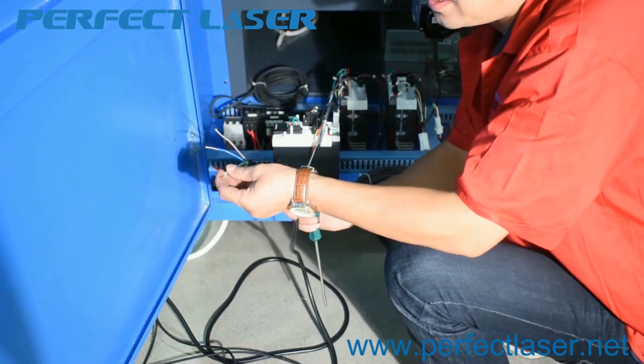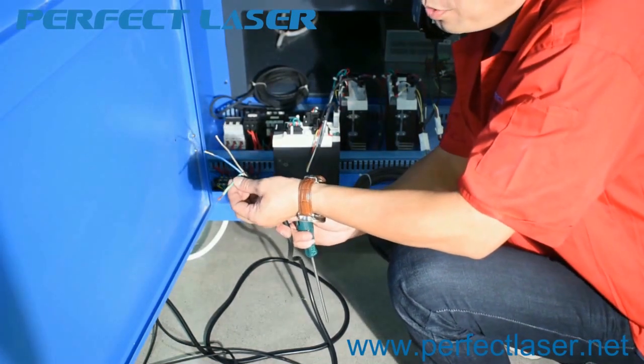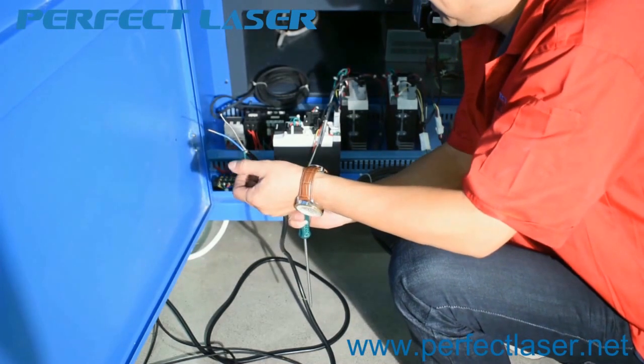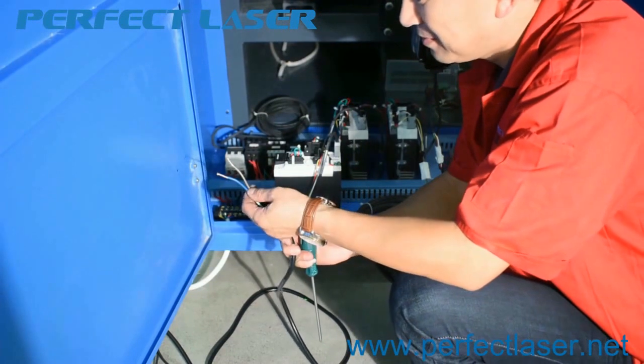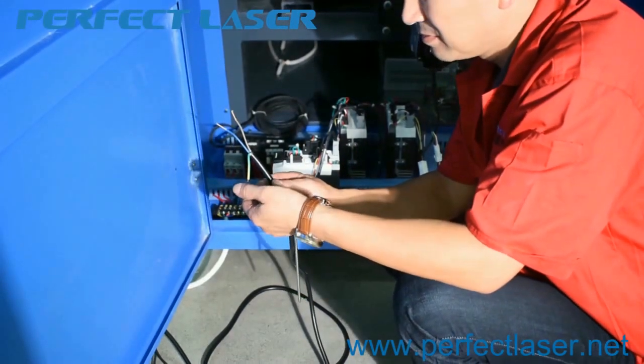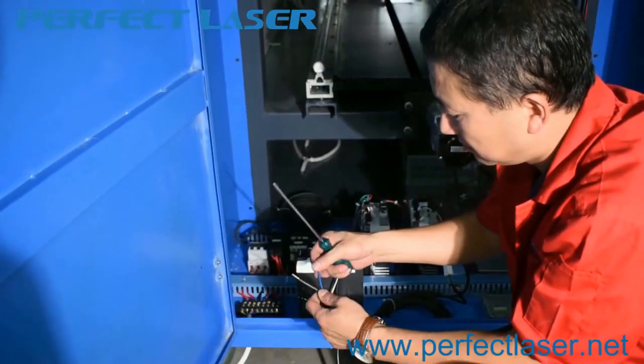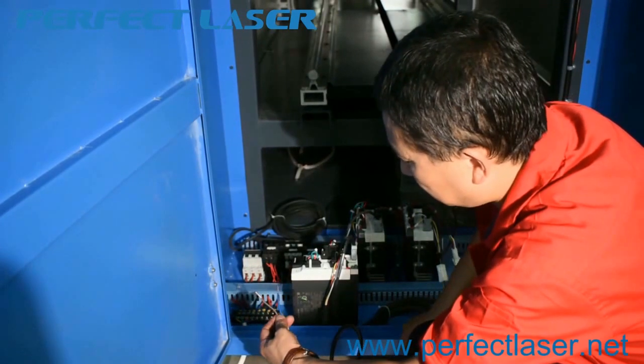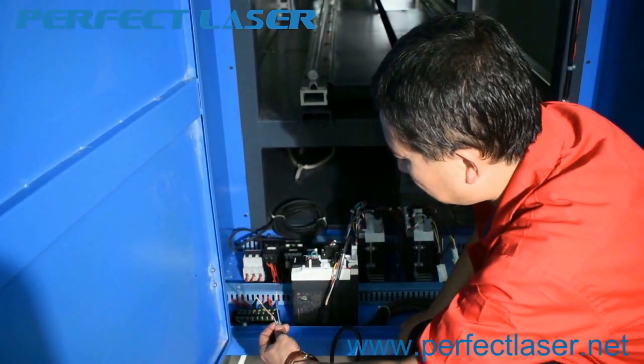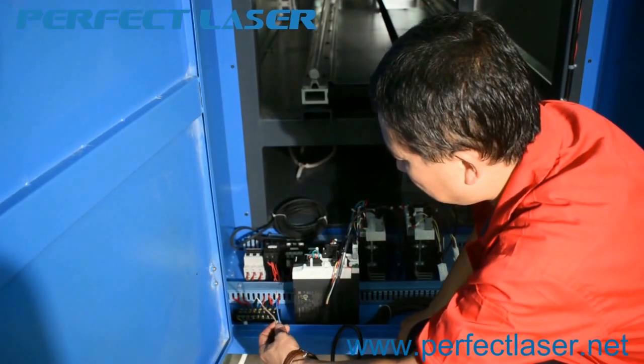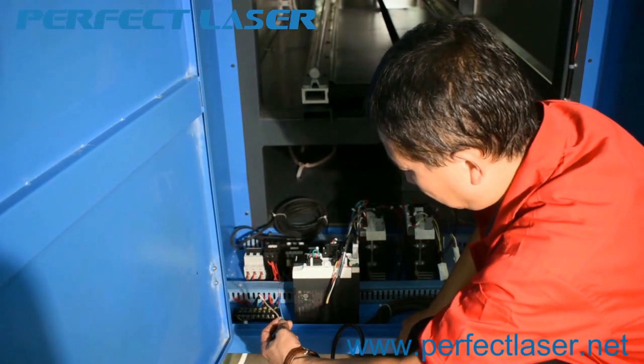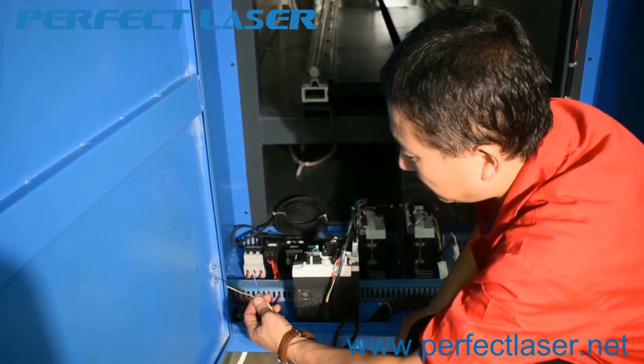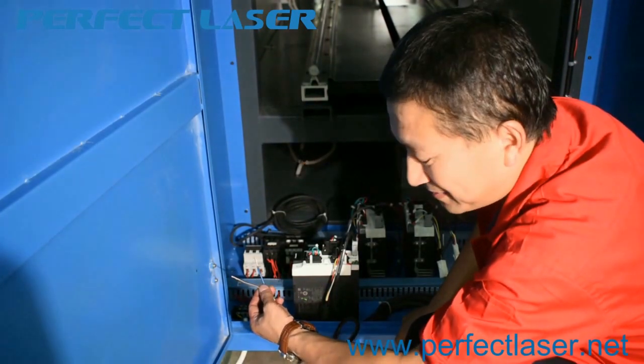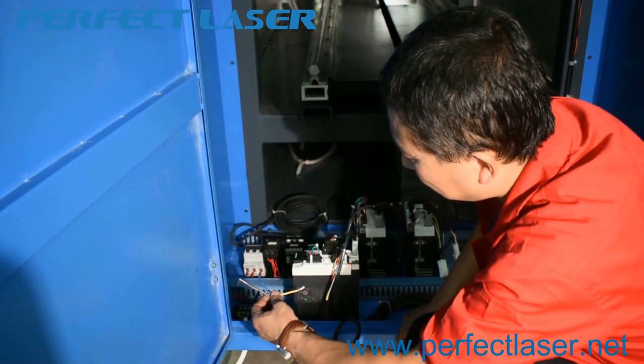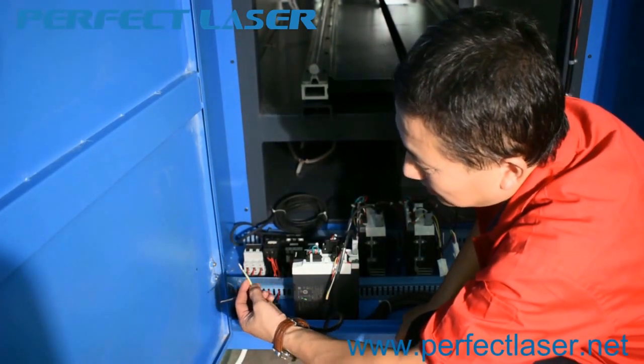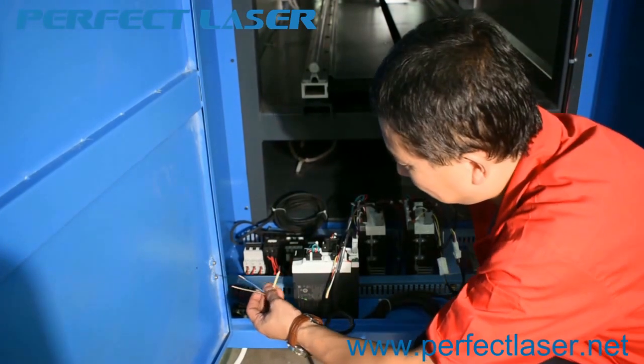These two are the power cables, and this is the ground cable. The gray one and the blue one are the main cable of the water chiller, and the green and yellow color is the grounding line. This is the main power cable of the water chiller. The water chiller is 220 volts, 50 Hz, and single phase. The gray color is the fire cable. The blue color is the zero cable. This green-yellow one is the grounding cable.